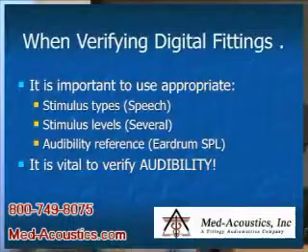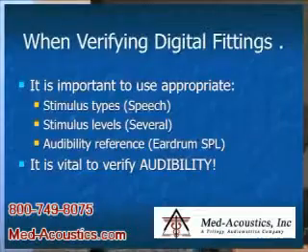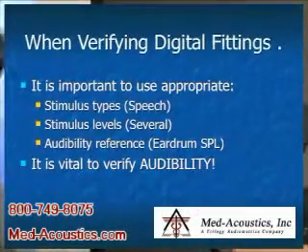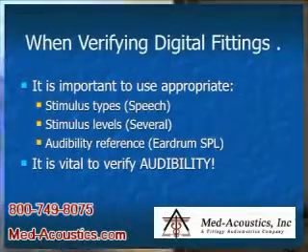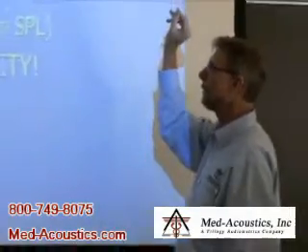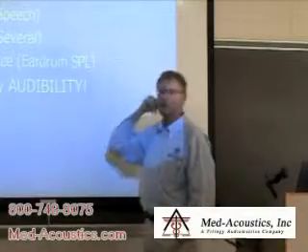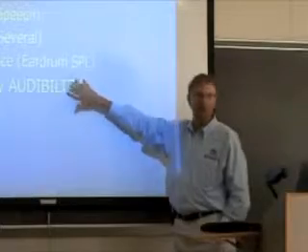So it's important to use a speech signal as the stimulus type, at several levels representing soft, average, and loud, and to make the measurement in the ear at the eardrum level. We are verifying audibility, and that's the best process.